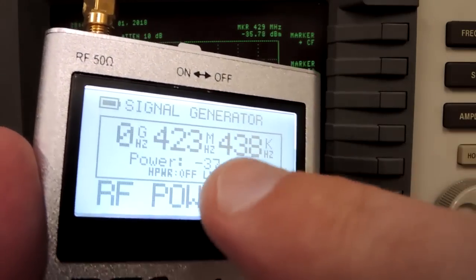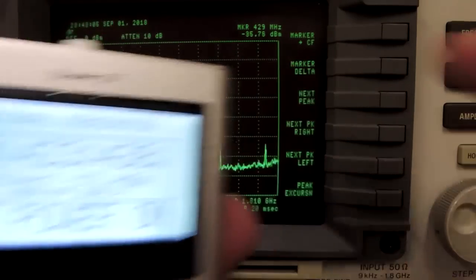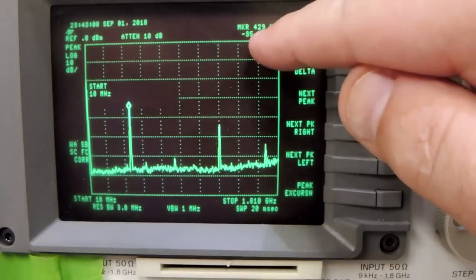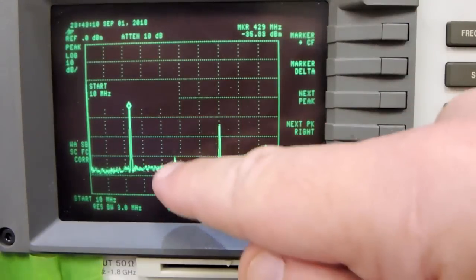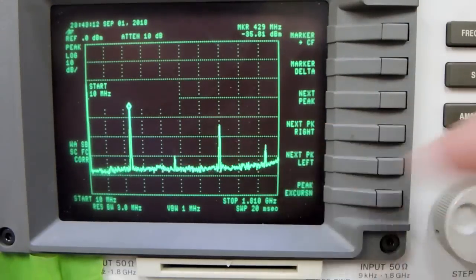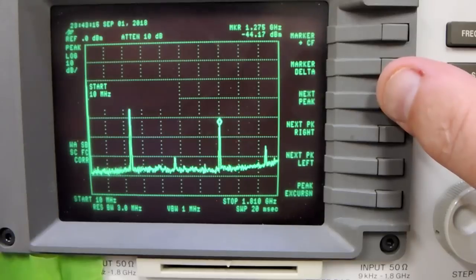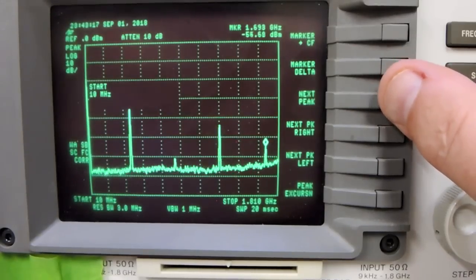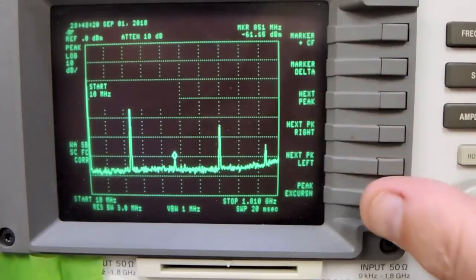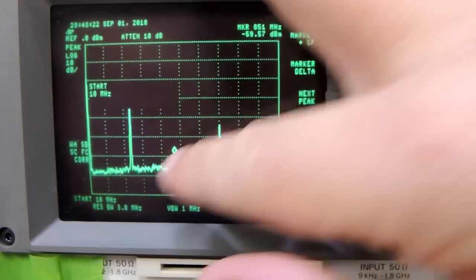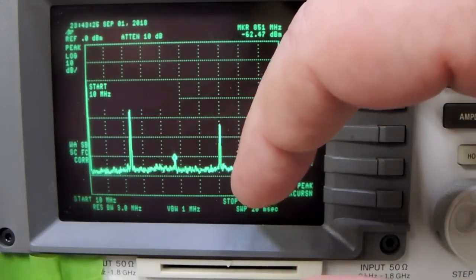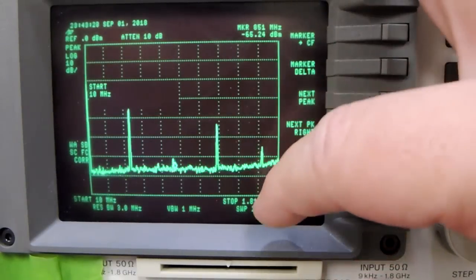To give some indication just how noisy the generator is, we're sitting at about 423 MHz. Here's the peak there. My spectrum analyzer says 429 MHz. But you can see all this junk sitting here, and it's fairly significant. The next peak at 1.2 GHz, 1.7 GHz, 851 MHz. So definitely not producing a sine wave. And that's disappointing because that really is a function of a signal generator.